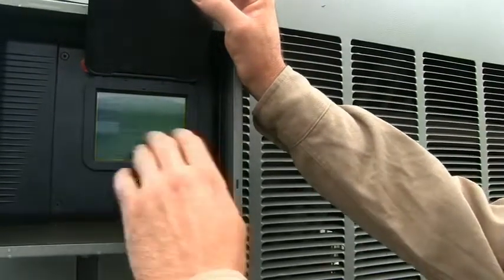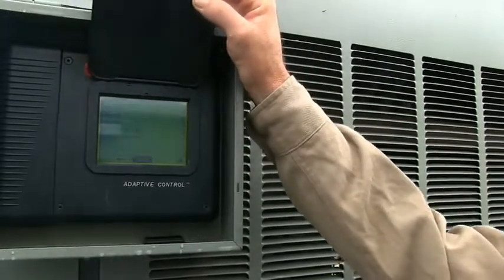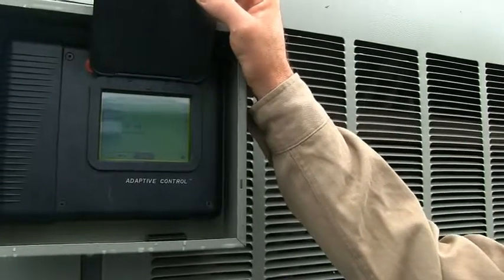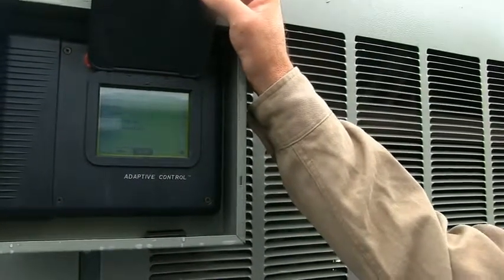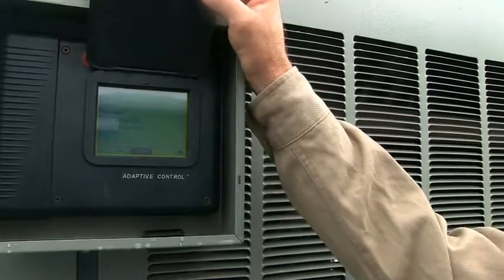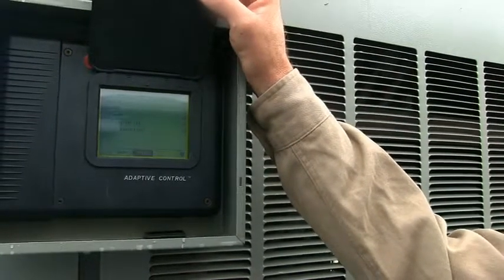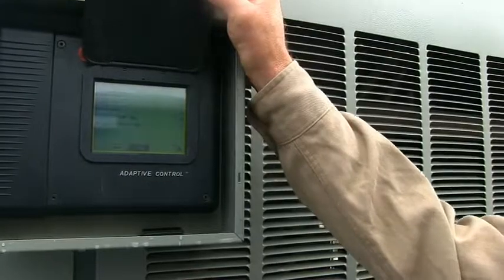So we'll scroll back one more time. We'll go to historic diagnostics. That'll tell you any prior alarms that this machine has had, as far as pump faults or compressor faults or anything related to chill water temps or pressures.